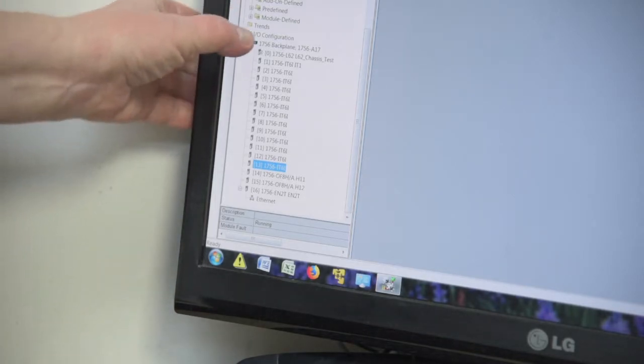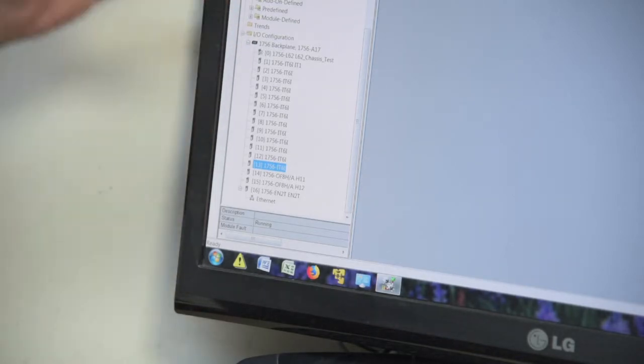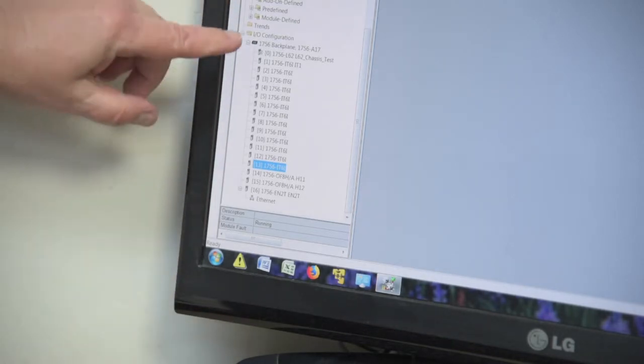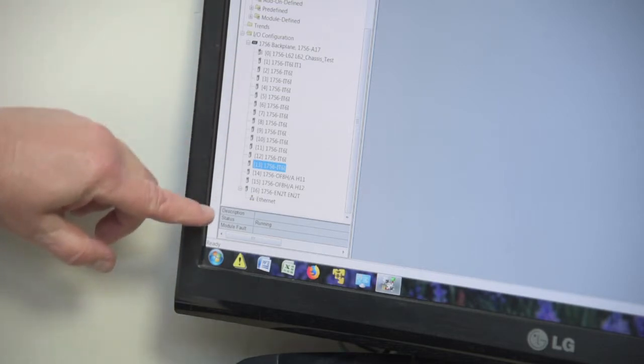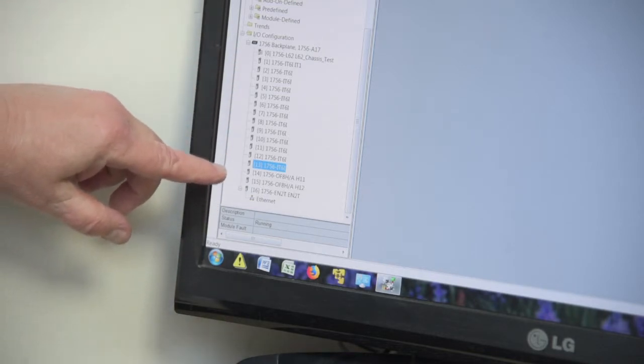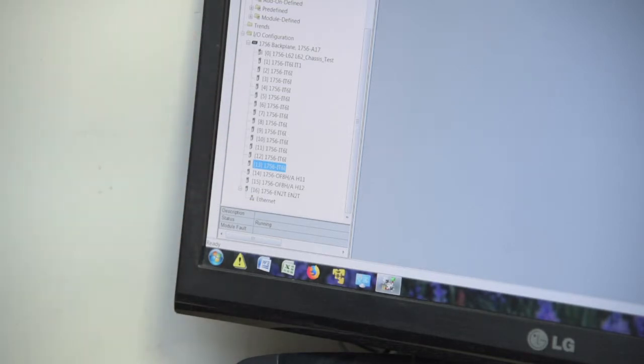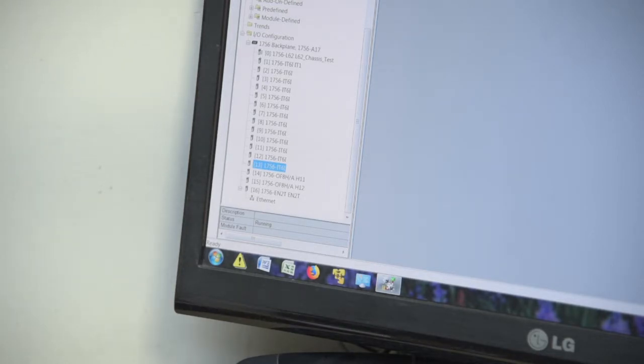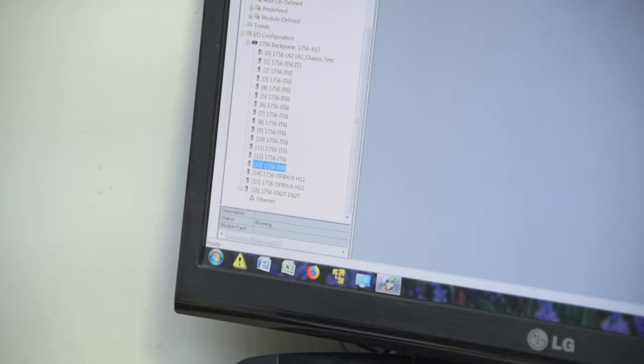So, there's our tree. It's just a dummy program with everything in it. There's all of our modules, we have no warnings on anything. So, we know that this combination, as it sits, chassis, power supply, and modules, everything's talking, and it's ready to go into service.